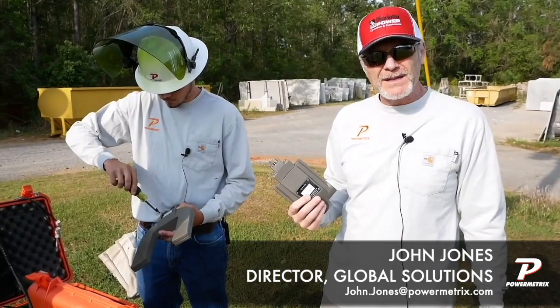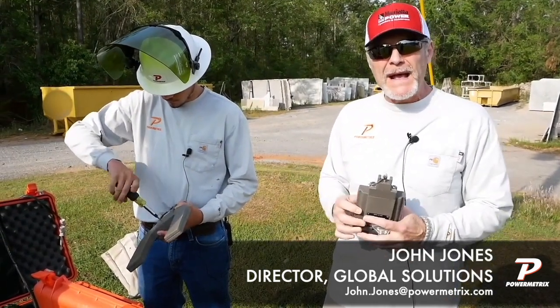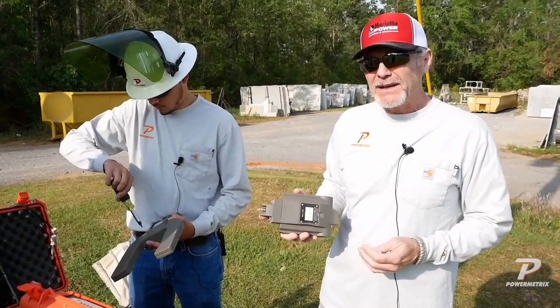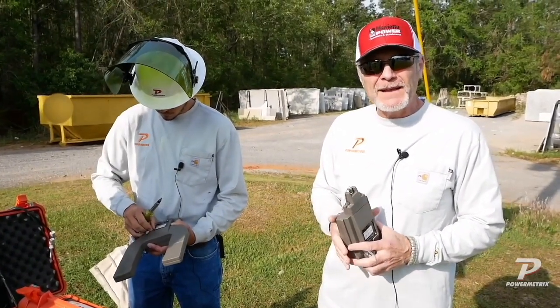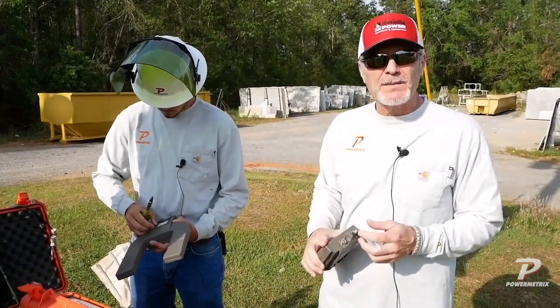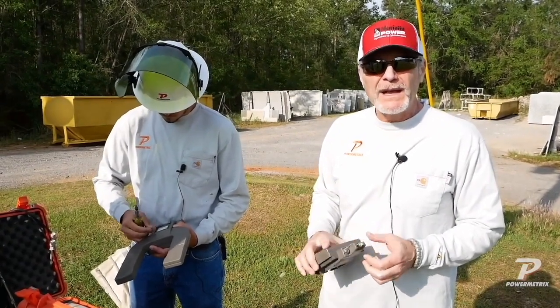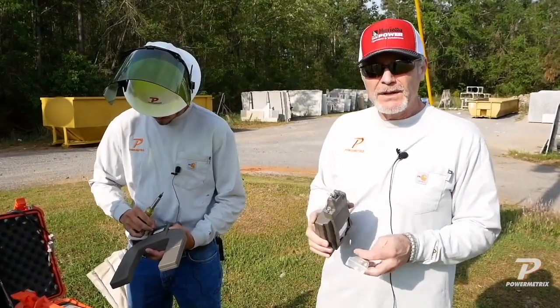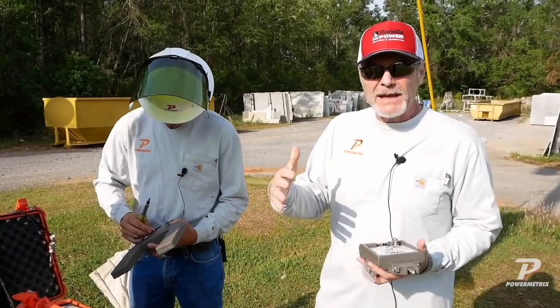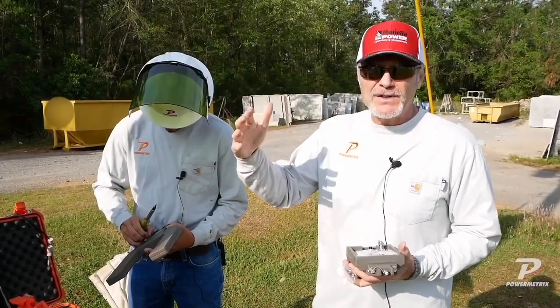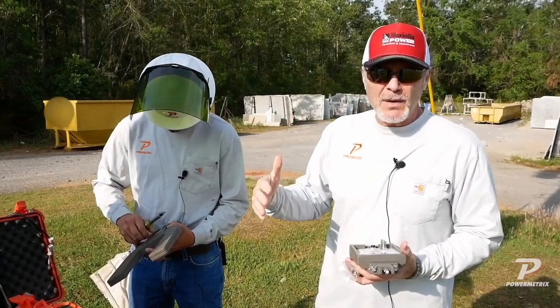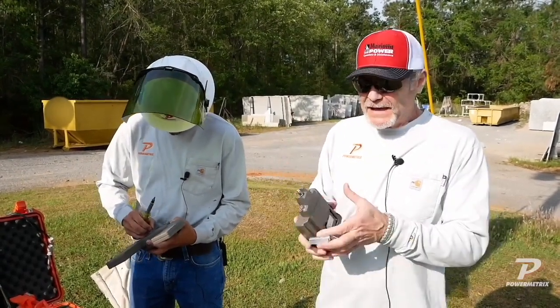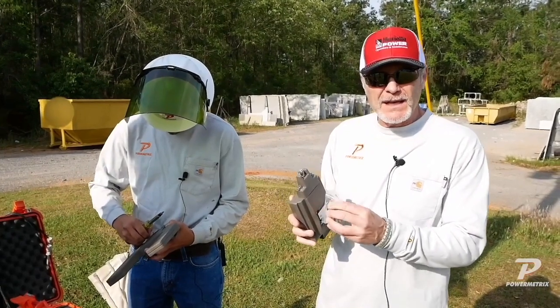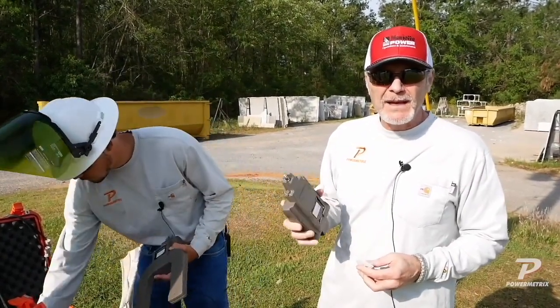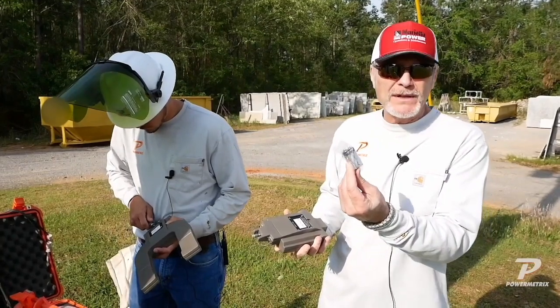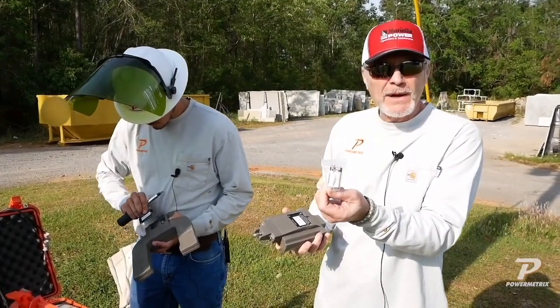But the problem is you've got to be careful. If it gets below 8.8, based on my experience in the field, once it gets below 8.8 I've had folks call in and say they're starting to get some crazy readings on their high volt probe. If the battery gets low, you'll typically start seeing high ratio errors, giving you some funny numbers. That's what happens when the battery starts getting low in this thing, and it doesn't like it once it's below 8.8. I've tested new ones and they're usually around 9.2, but once they get below 8.8 you can start having issues.